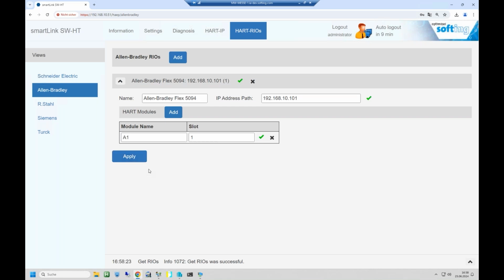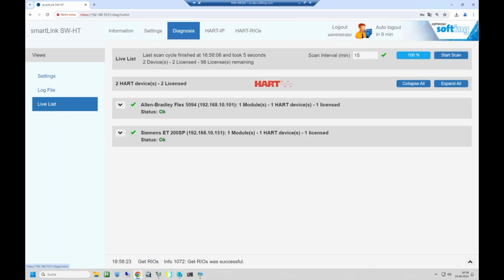Now, the most important thing is that we have the HART devices connected to the Ethernet based Allen Bradley Remote I/O, which is Flex 5094. The SmartLink software version needs to be configured so I can have access to the HART devices. Once I go to diagnosis, I see three options here.